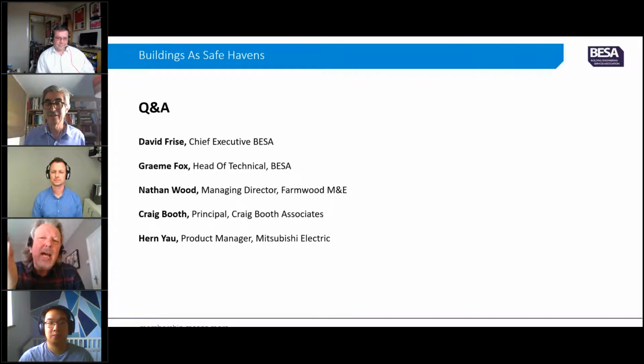It's happening much less now, but until quite recently there was a common misapprehension where people were saying, my CO2 is under 5,000 ppm, the Health and Safety Executive says it shouldn't exceed 5,000 ppm, so everything's fine—which was a massive misunderstanding of the standard set by the HSE, which was for occupational exposure.